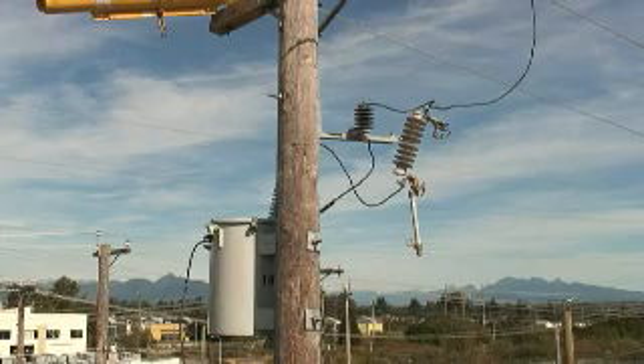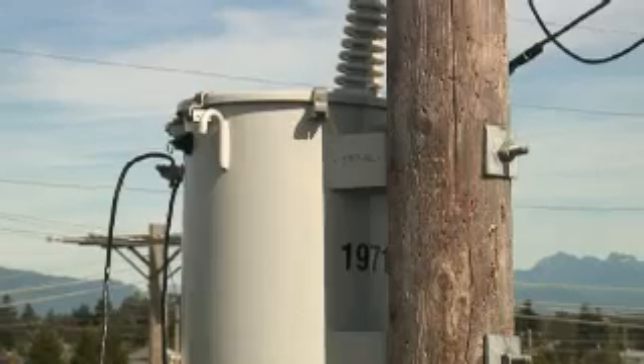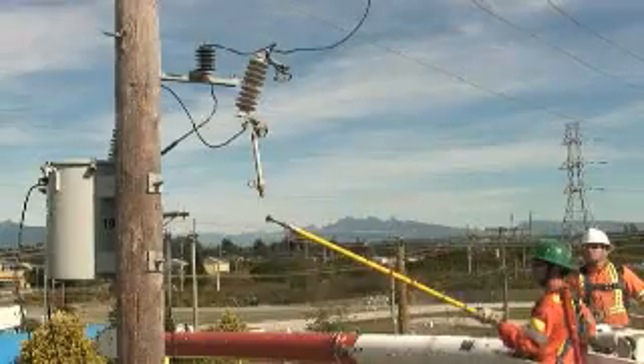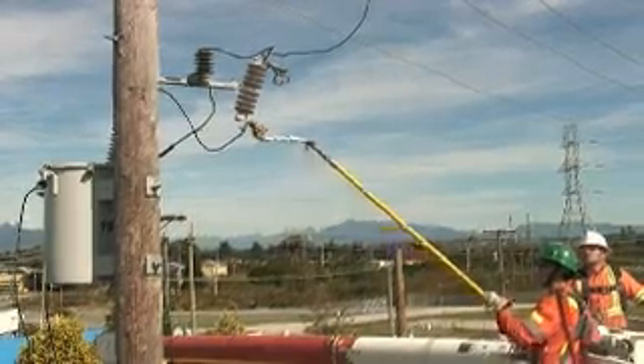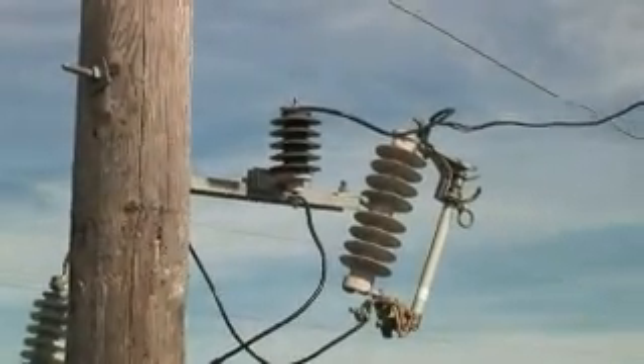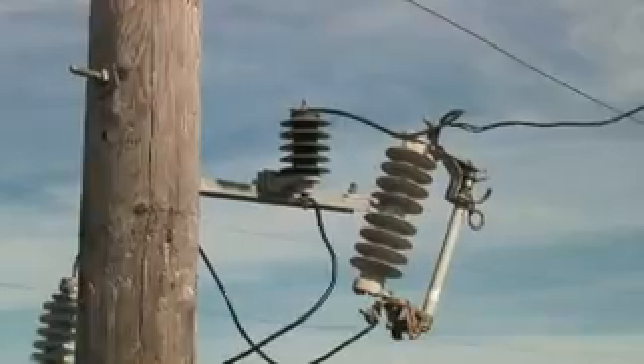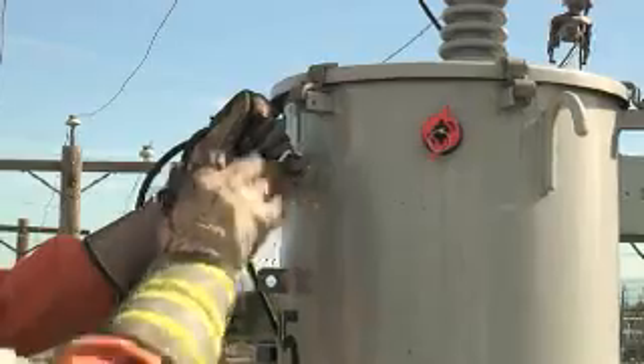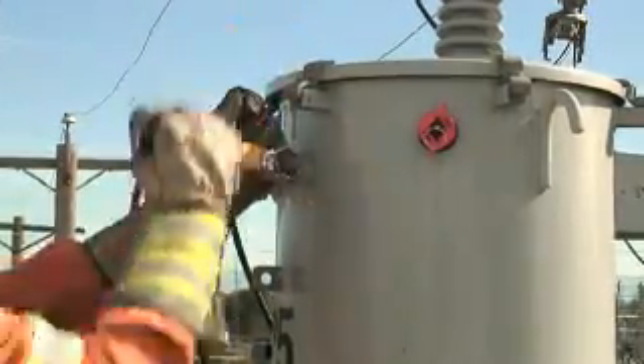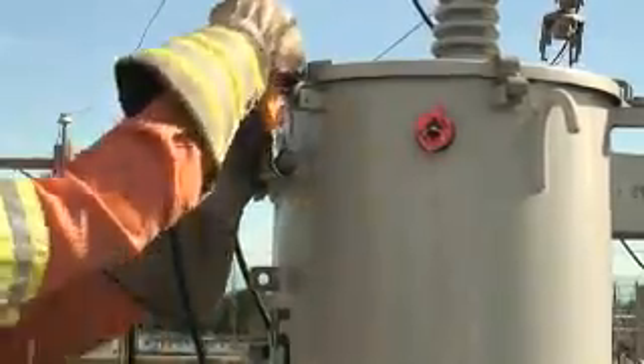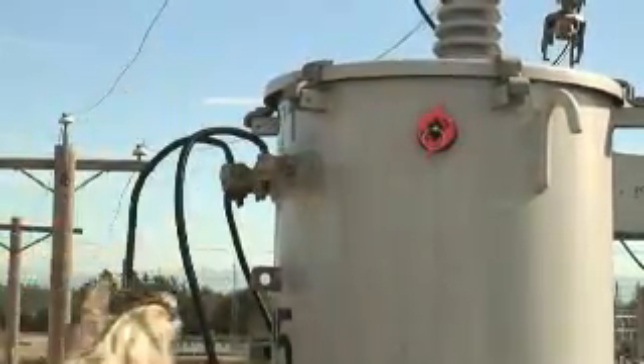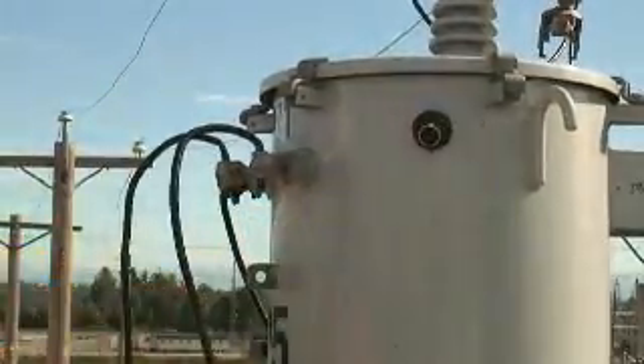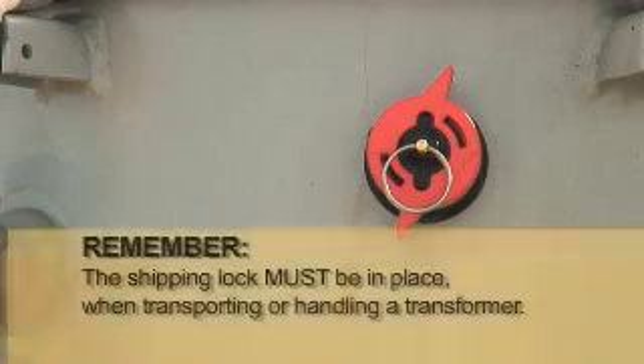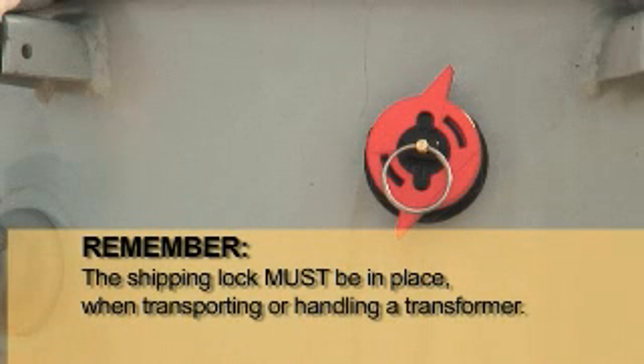If the cutout fuse is open but the IFD is not activated, chances are the transformer is okay to re-energize, providing all normal fault checks are done. Nothing can be considered 100% when it comes to safety. Installing IFD-equipped transformers is almost identical to other transformers. The only difference in the process is the removal of the shipping lock once the transformer is mounted. Remember, the shipping lock must be in place when transporting or handling a transformer with an IFD installed.